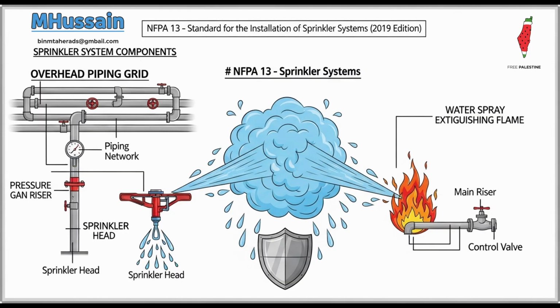profile. Okay, let's move to the advanced protection schemes designed specifically for these high-hazard storage environments. Control mode specific application, CMSA, and ESFR systems. These utilize much higher flows and pressures than standard sprinklers. Yeah, the design requirements here are highly dependent on numerous variables: the commodity type, the storage height, the ceiling height, even whether the system is wet or dry pipe. For high-density rack storage, you often need ESFR or CMSA sprinklers with really large K factors, like K25.2, which means massive water delivery is needed. What is the fundamental difference in mechanism between CMSA and ESFR? How do they work differently?